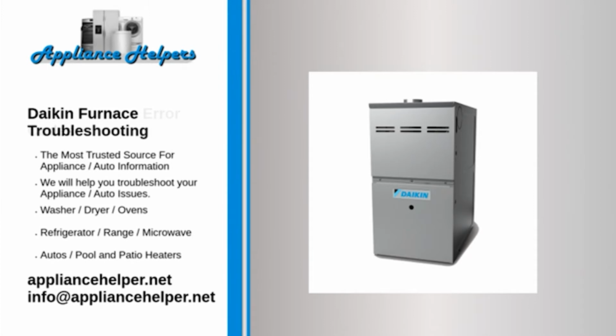If you're looking for help fixing your Daikin furnace, look no further. Our comprehensive Daikin Furnace troubleshooting guide will explain common issues, provide tips, and show you how to read your model's error codes. Not heating. The electrical system that provides power to your furnace has either shorted or blown the power switch. Reset your furnace's circuit breaker. If it is blown, you'll have to replace it.